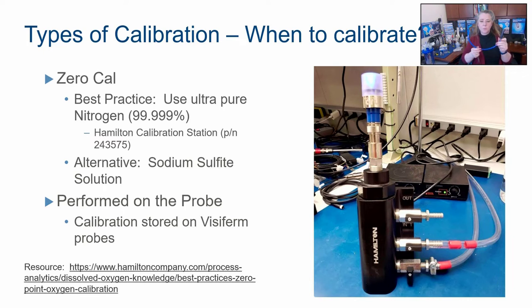You take ultra pure 99.999% nitrogen gas. You don't want anything less than that, five nines. And you need to flood the end of your sensor with nitrogen gas for a while so that there's no possible oxygen there. You don't want to immediately blanket this with flowing gas, because when you take high pressure gas, which in a tank is around 2,340 PSI, and you get it down to where you need it, which is 2 to 3 PSI, it gets really cold. It's called the Joule-Thomson effect.